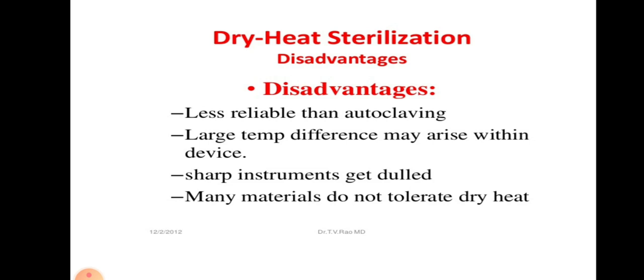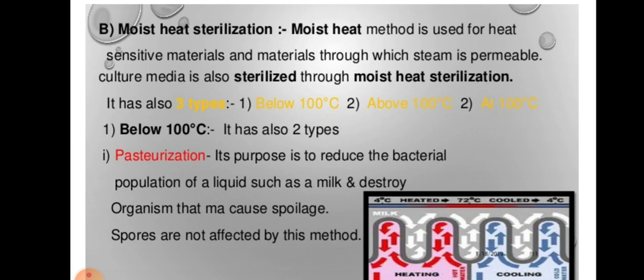Disadvantages of dry heat sterilization: it is less reliable than autoclaving. Large temperature differences may arise within devices. The sharp instruments get dulled. Many materials do not tolerate dry heat. Moving on to the second mechanism, moist heat. Moist heat method is used for heat-sensitive materials and materials through which steam is permeable, like culture media.